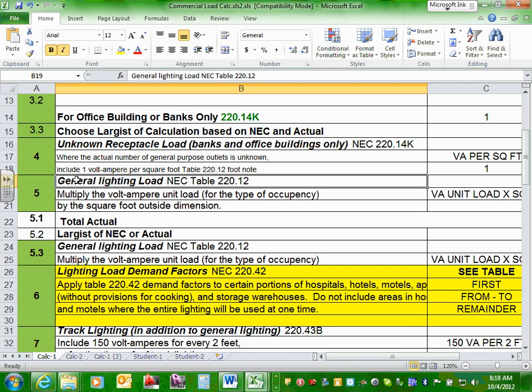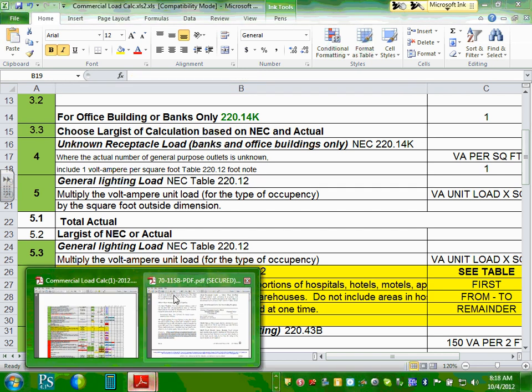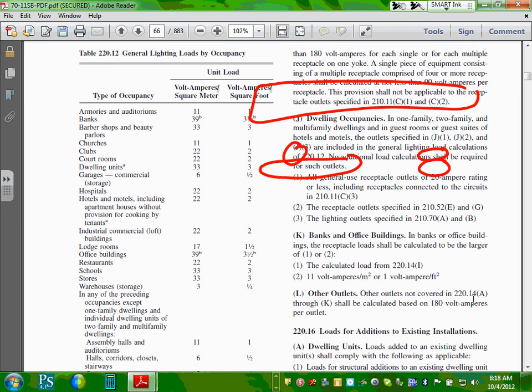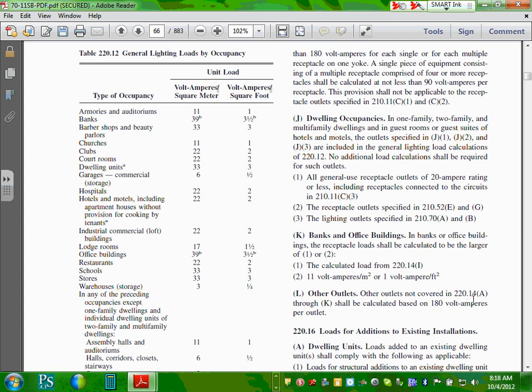General lighting. We went to Table 220.12. For an office building the volt-ampere per square foot is 3.5 VA/sqft — you'll see the 'B' footnote next to it, which tells you that you also need 1 VA/sqft for receptacles. For the demand: is there any demand for office building lighting? No. We apply a demand of 100% for the office building. There is no demand table for office building lighting.